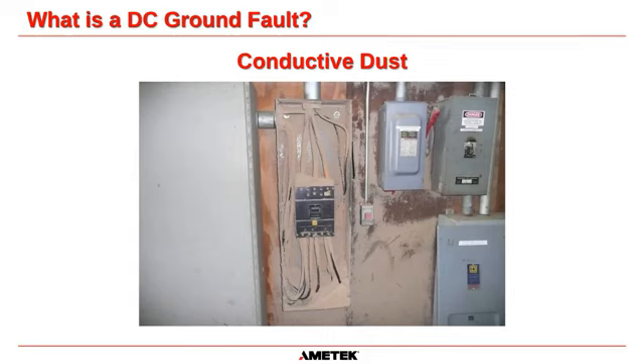Another way we can do it is conductive dust. This is an actual picture. I'm guessing it's from a sawmill or a paper mill or something. I'm pretty sure they haven't been in this breaker for quite a while. You can see there's a huge amount of dust in this bottom left-hand corner, but more importantly, there is a huge amount of dust across these three conductors here. And if that dust is conductive, it is definitely going to cause a short or a ground fault or something bad. I just thought this photo was a very good representation of how dust can cause faults.